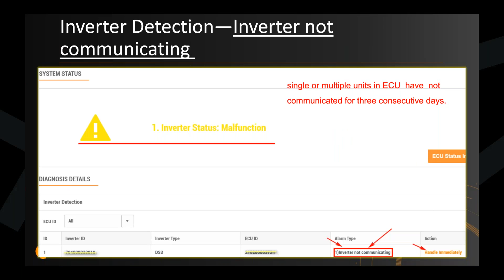Another issue that we've also seen is the inverter not communicating. You can very easily see that on the module view where it says NC, but if you look at the inverter itself, you see no data. For those types of scenarios, it can be, one, the microinverters are not close to the ECU. Two, there is something causing interference between the microinverters and the ECU. Or three, the microinverters do not have any panels on them. One note also is that a microinverter is only powered if it has DC voltage. If you have AC voltage only on the microinverter, you won't be able to get any communication, because it's purely powered off of the panels, the DC voltage.